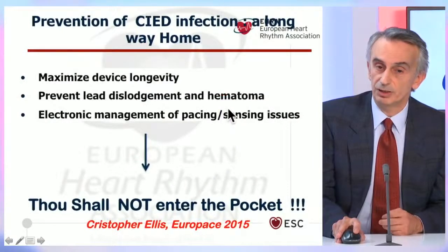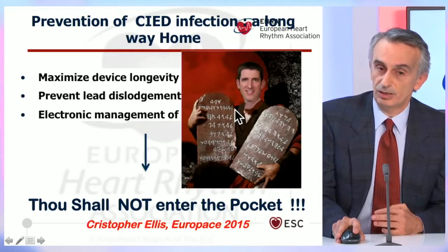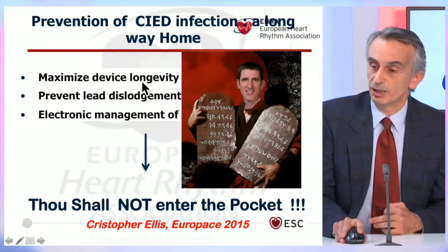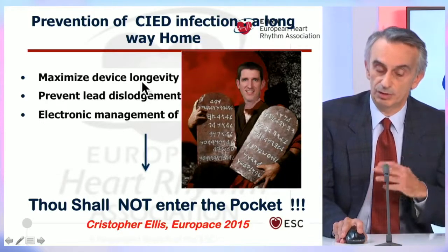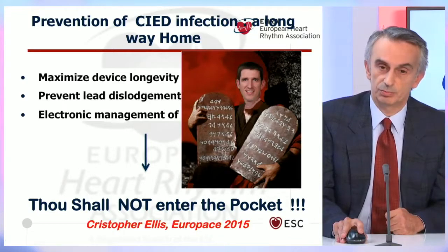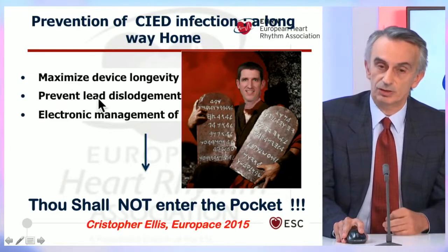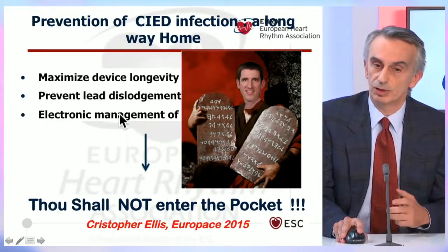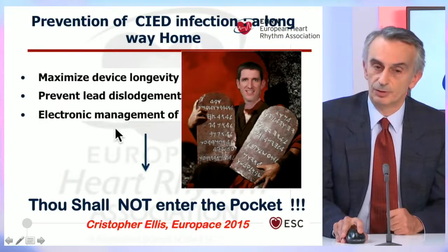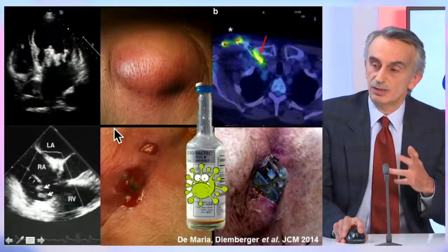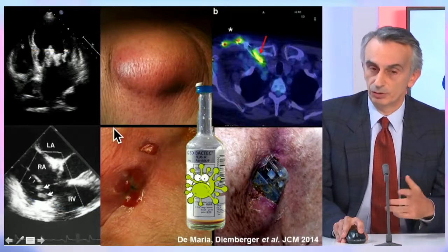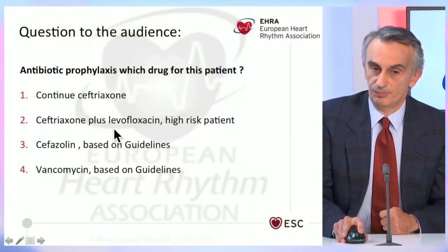So avoiding pocket opening is a mandatory strategy, whether we are looking at broad topics like device longevity maximization, prevention of lead dislodgement by active fixation, or electronic management of issues. This is the leading door to endocarditis.